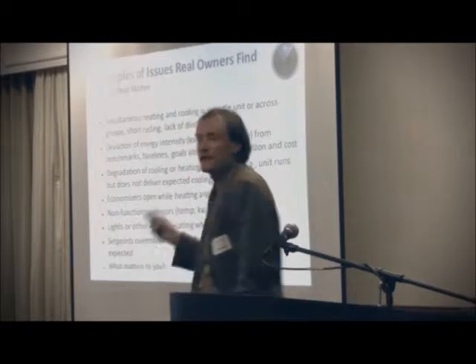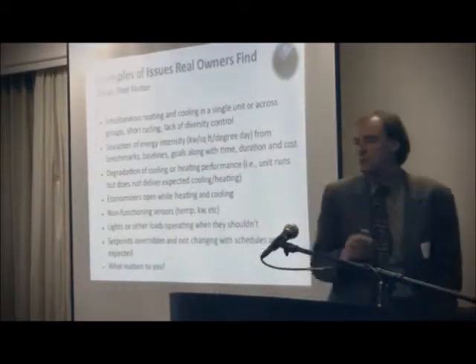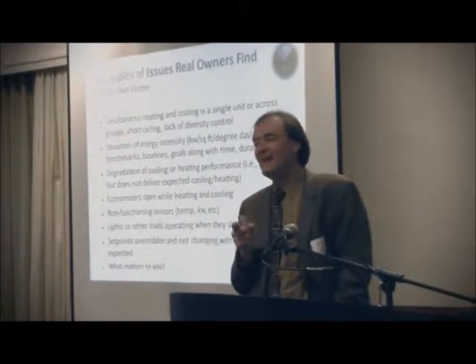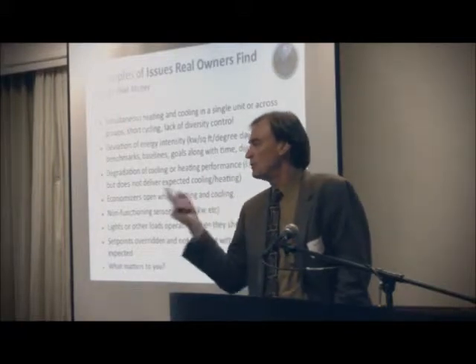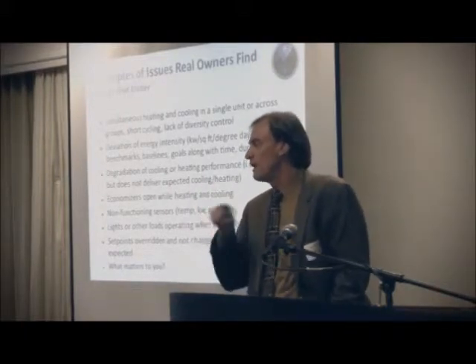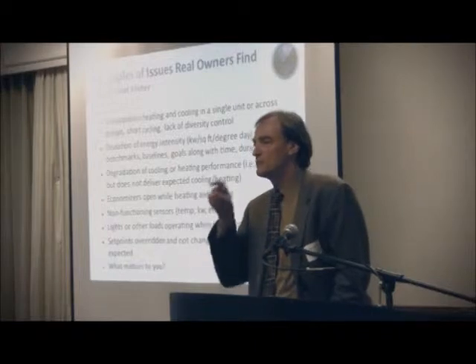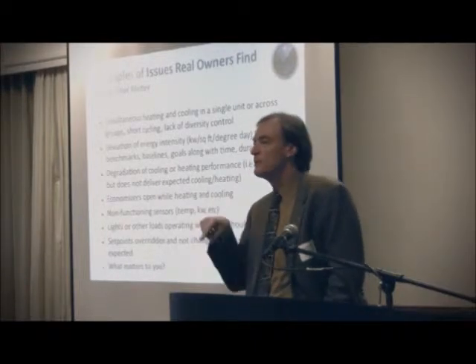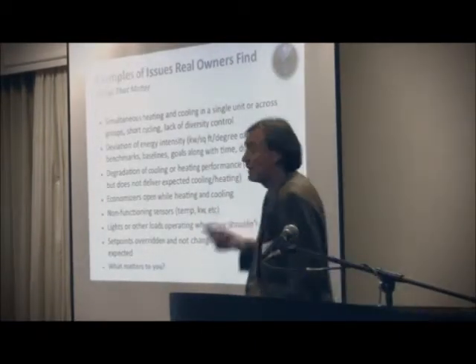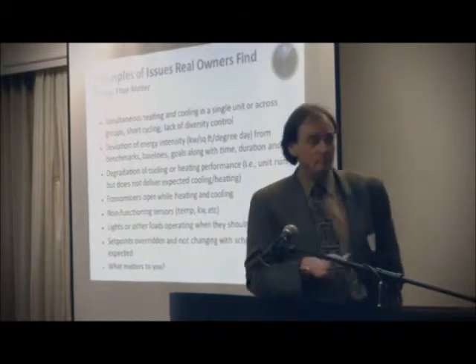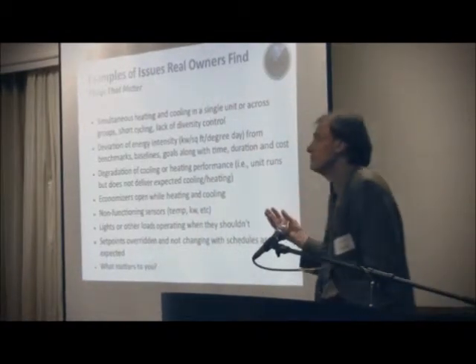Then there's lack of diversity control. To achieve the demand response program and get those checks, we implemented something called diversity control—say, I have 10 rooftops, but my program only allows 7 of them to run at a time, picking the 7 that need it most. We set that up as a good program. I saw it work once. Is it working today? How do we know?